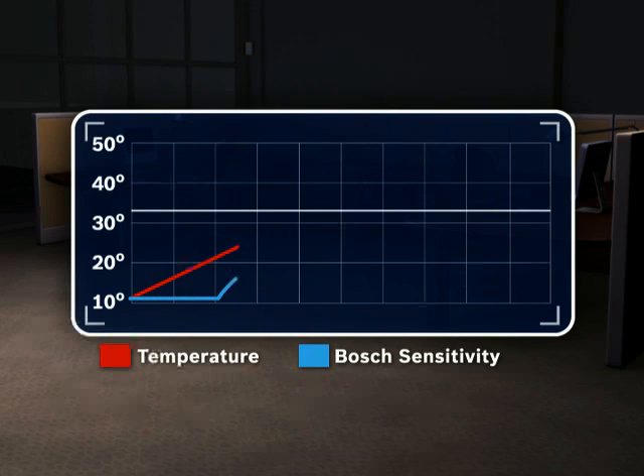the sensor gain increases until the room temperature reaches 33.3 degrees centigrade, or 92 degrees Fahrenheit, the temperature of human skin. But once the ambient temperature exceeds 33.3 degrees centigrade, or 92 degrees Fahrenheit, the sensitivity decreases, minimizing false alarms.